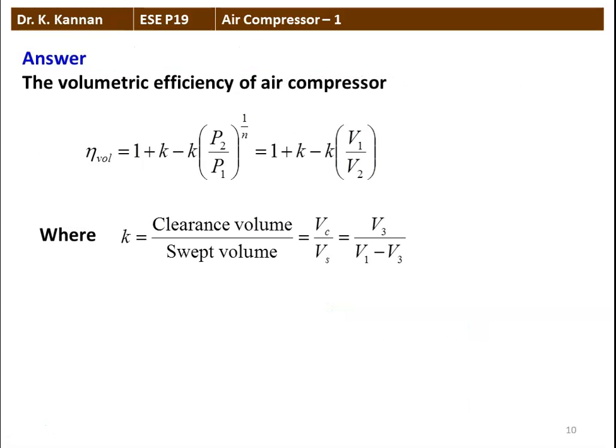The volumetric efficiency is defined as: η_vol = 1 + K − K·(P2/P1)^(1/N), or equivalently 1 + K − K·(V1/V2), where K is the clearance ratio, which is the clearance volume divided by stroke volume, V_C / V_S, or V3 / (V1 − V3).